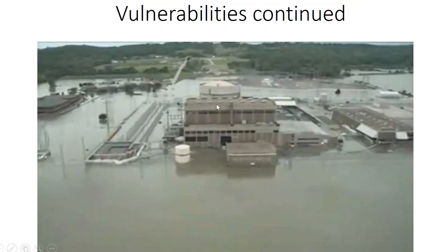So your buildings would start getting cold as that aux boiler ran out of fuel and things would start freezing. You'd lose your amount of fuel oil over here in FO1, and then if you lost offsite power for any reason, well, all of a sudden you're in a case where, hey, how do we get power here to keep cooling things down? Fortunately, we had quite a bit of time to deal with that at the time, but had this happened at a less opportune time, we'd probably still be hearing about Fort Calhoun.